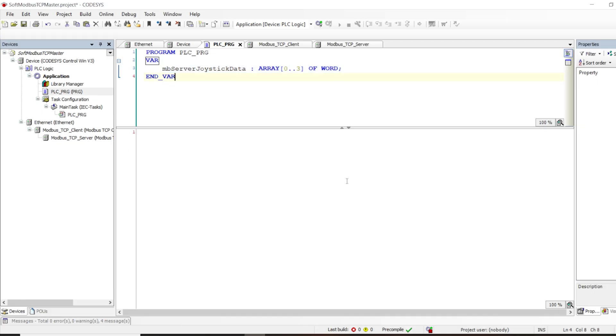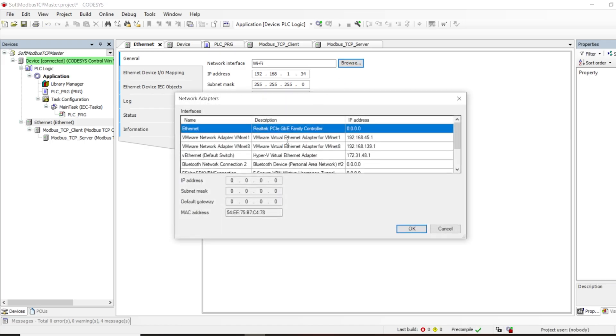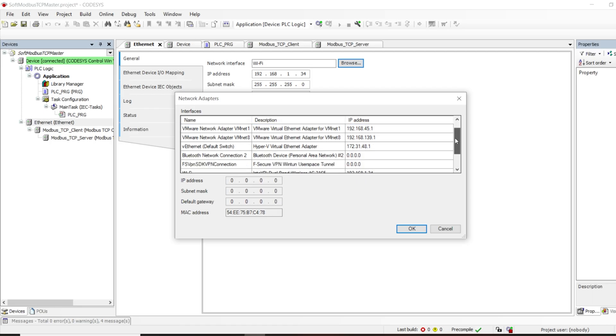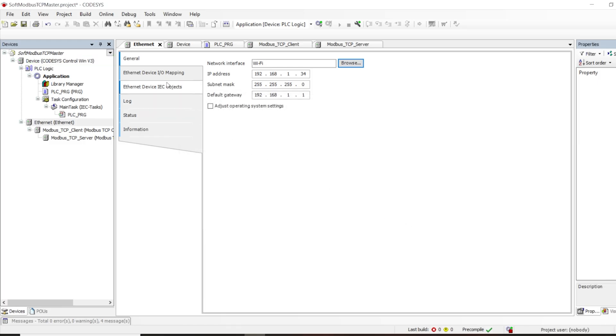One more thing — since the soft PLC runs on your computer, your PC may have multiple Ethernet interfaces, so you need to define which interface to use for this communication. Double-click on Ethernet, go to Ethernet Interface, and browse. I have multiple interfaces on this laptop; the one connected to the same network as my server is my Wi-Fi interface at 192.168.1.34. I'll select that, and now we're done with configuration.